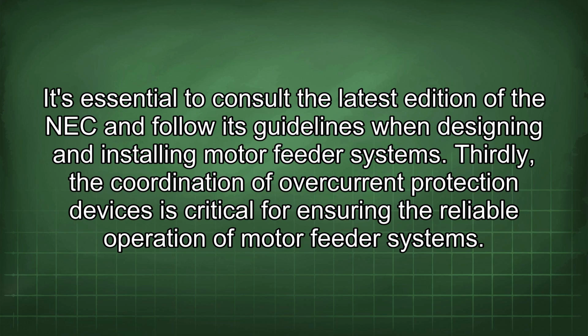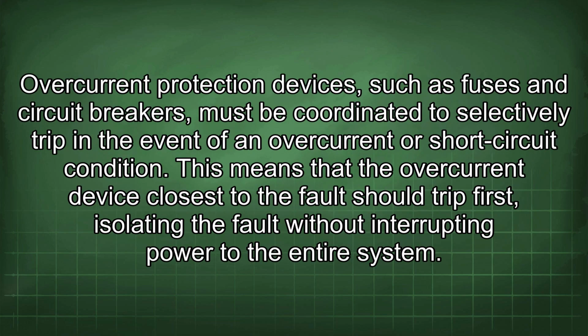It's essential to consult the latest edition of the NEC and follow its guidelines when designing and installing motor feeder systems. Thirdly, the coordination of overcurrent protection devices is critical for ensuring the reliable operation of motor feeder systems. Overcurrent protection devices, such as fuses and circuit breakers, must be coordinated to selectively trip in the event of an overcurrent or short-circuit condition. This means that the overcurrent device closest to the fault should trip first, isolating the fault without interrupting power to the entire system.